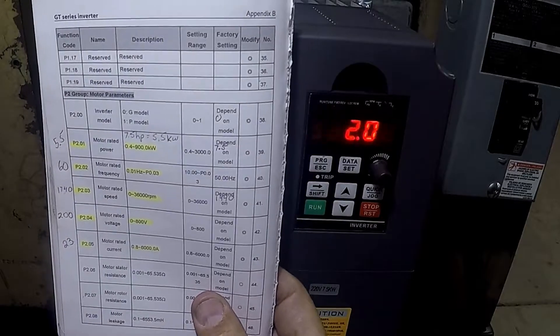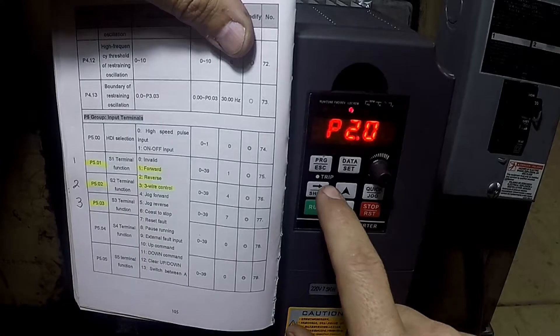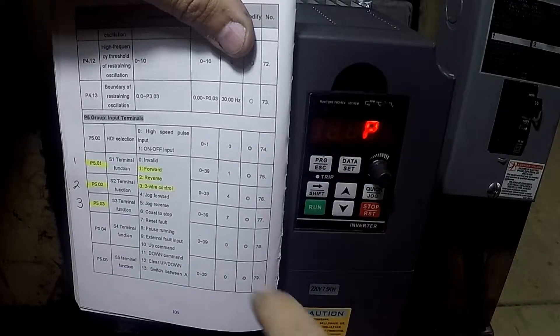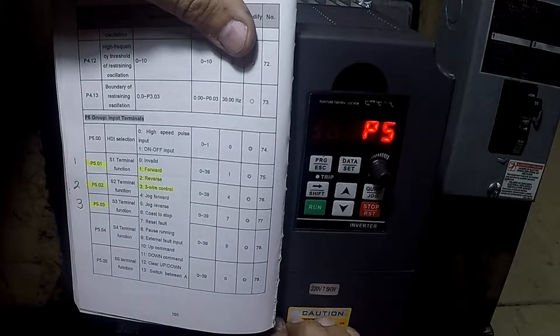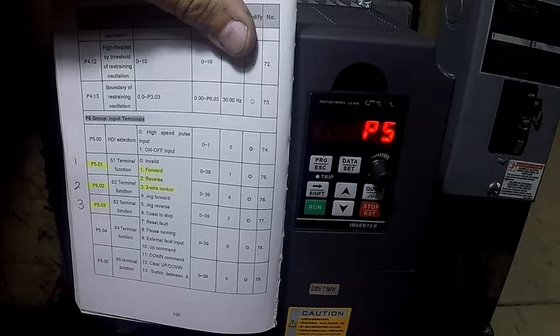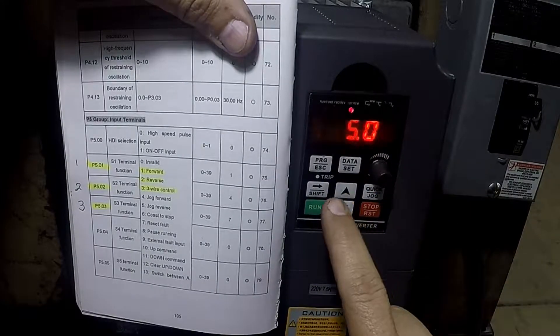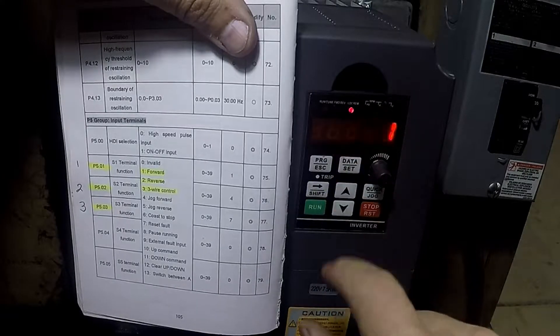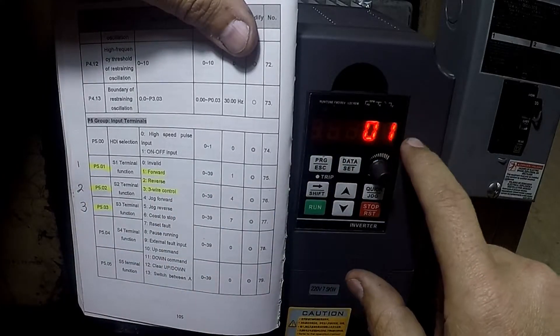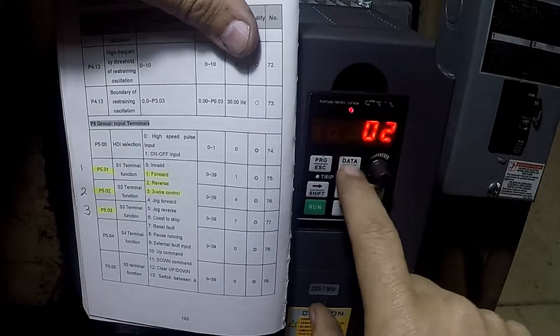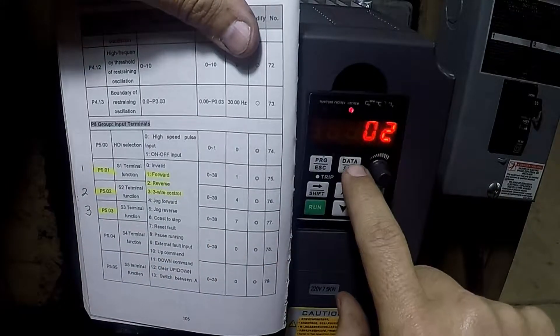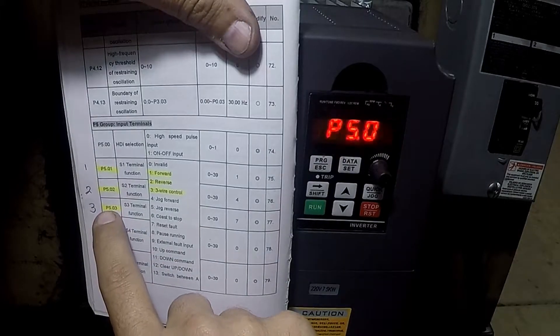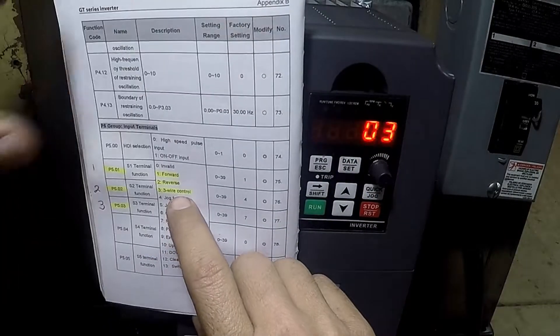For the next part I'm going to parameter group 5, which is the input terminals. That's where the wires are wired into the S1, S2, and S3 and the common down here. P5-0 has to do with the way the input comes, I'm not worried about that. P5-1 is actually set to the number one which is forward. P5-2 is set to the number two which is reverse. P5-3 is set to the number three which is the three wire control.